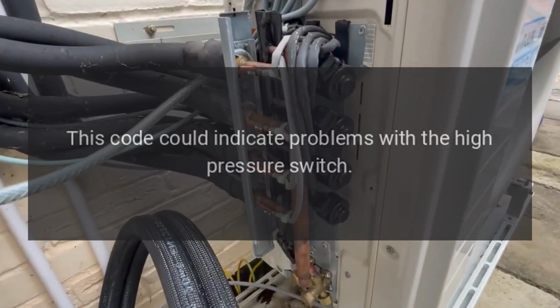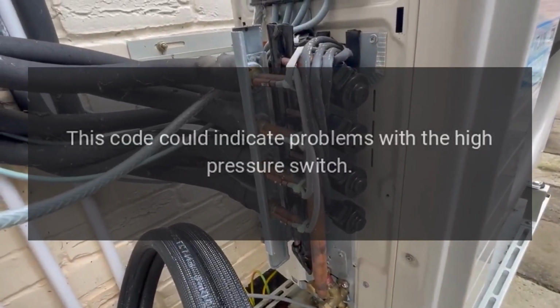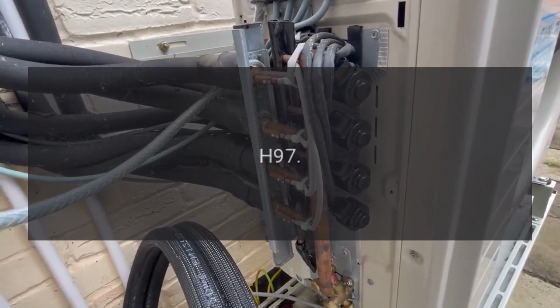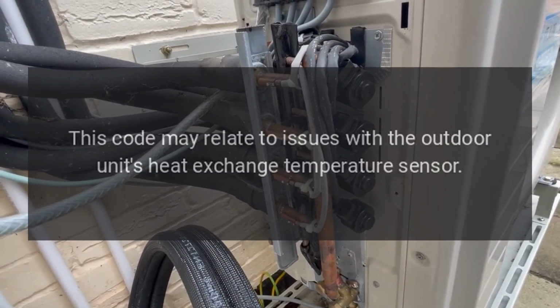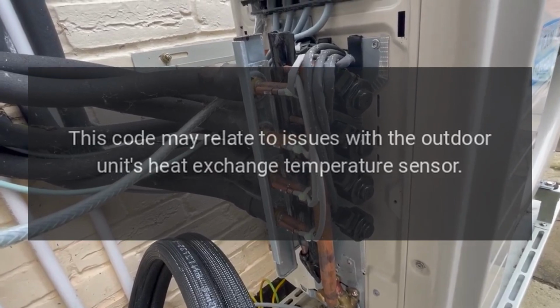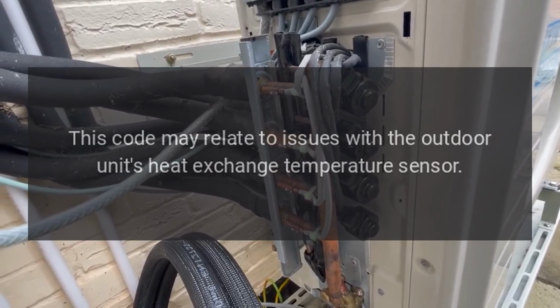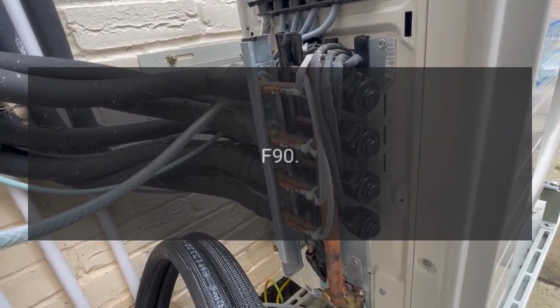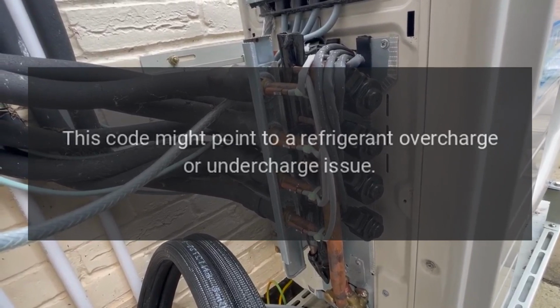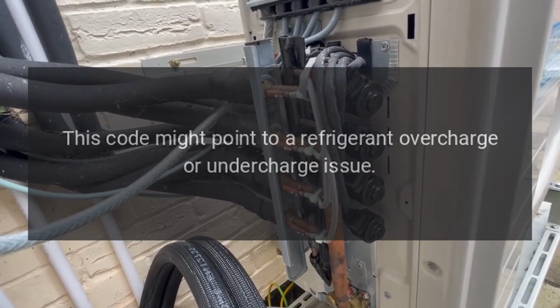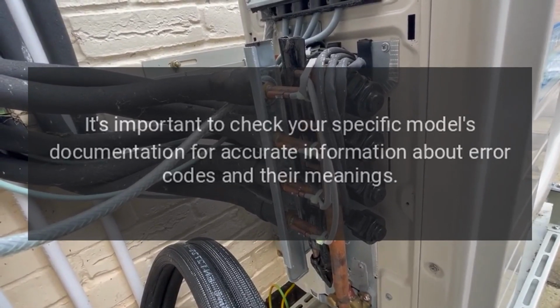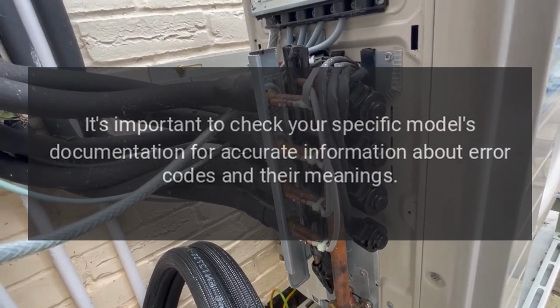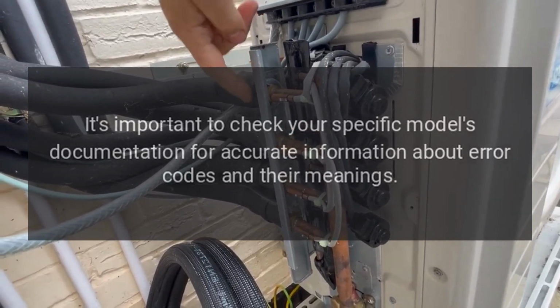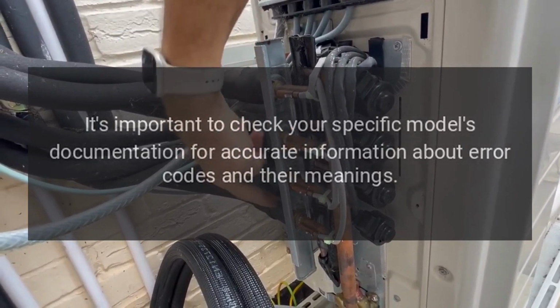H30. This code could indicate problems with the high pressure switch. H97. This code may relate to issues with the outdoor unit's heat exchange temperature sensor. F90. This code might point to a refrigerant overcharge or undercharge issue. It's important to check your specific model's documentation for accurate information about error codes and their meanings.